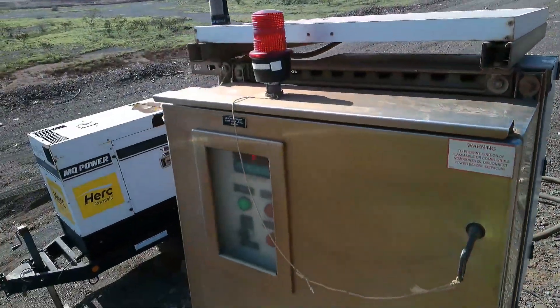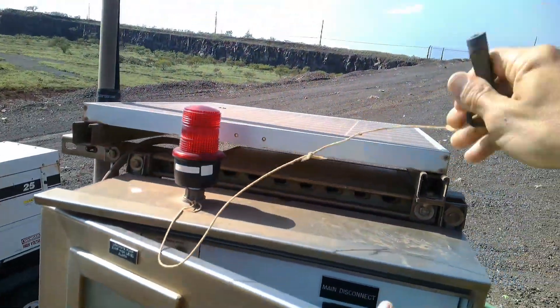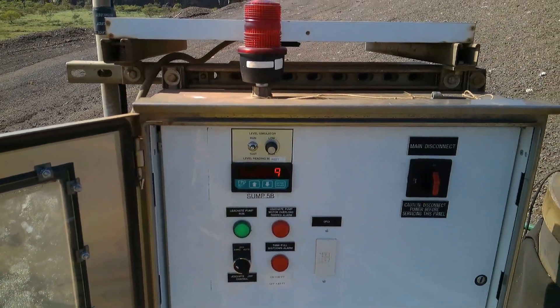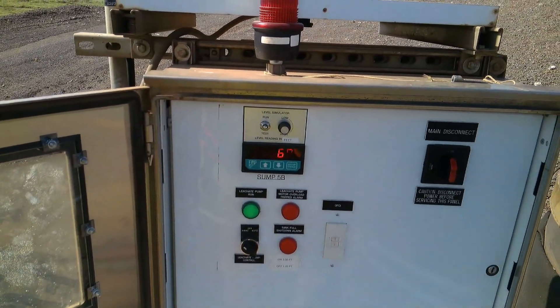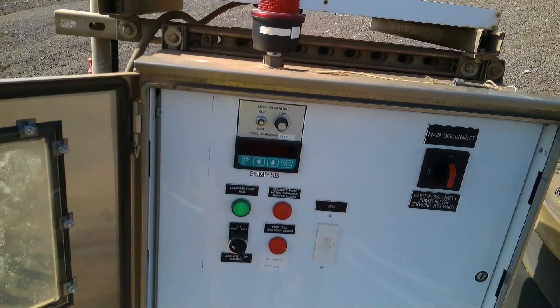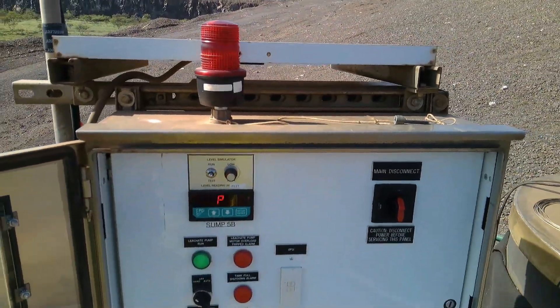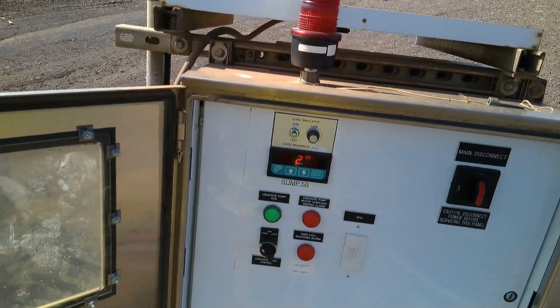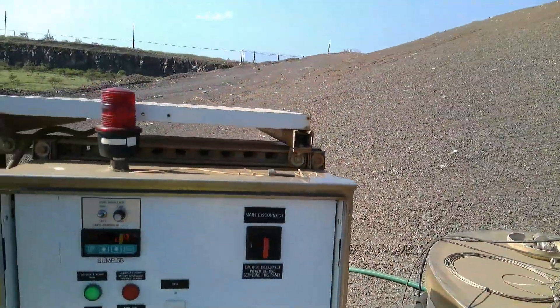Alright, hey guys, here we are on site. Kind of interesting — maybe I'm at the wrong place — but the transducer appears to be working. It says 2.69 feet on our display there. Sump pump's running in hand. Let me call my operator and see what's wrong, because it's entirely possible I'm at the wrong place.